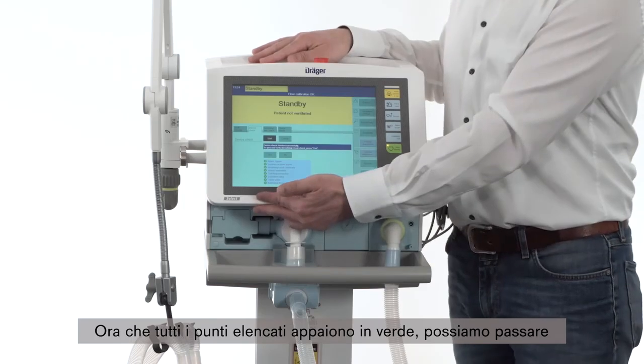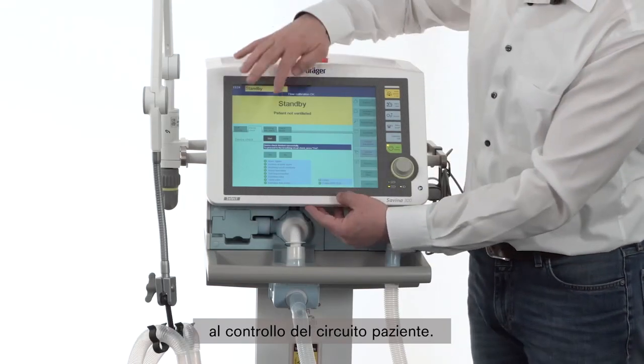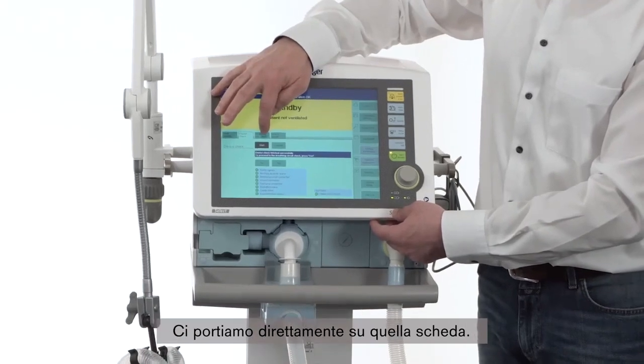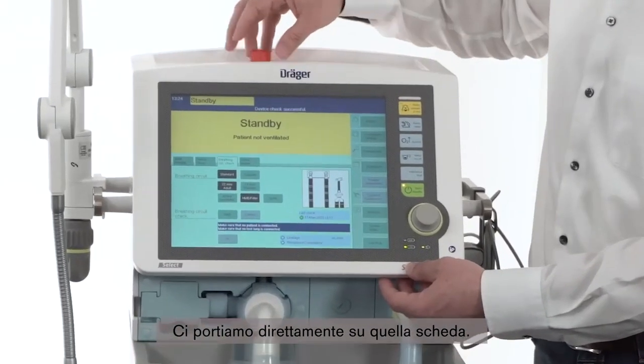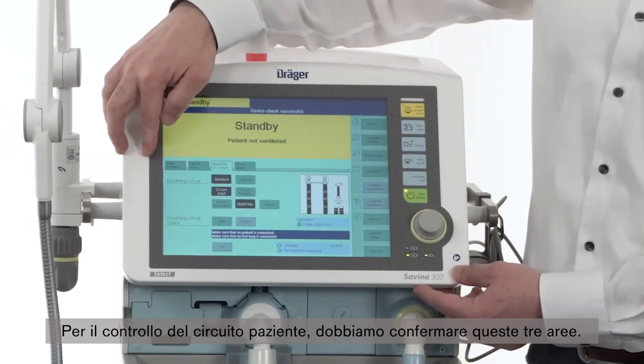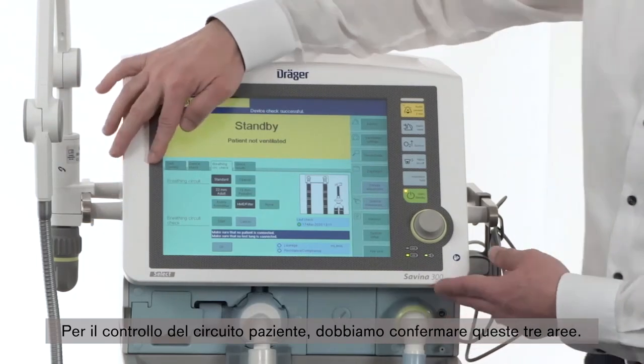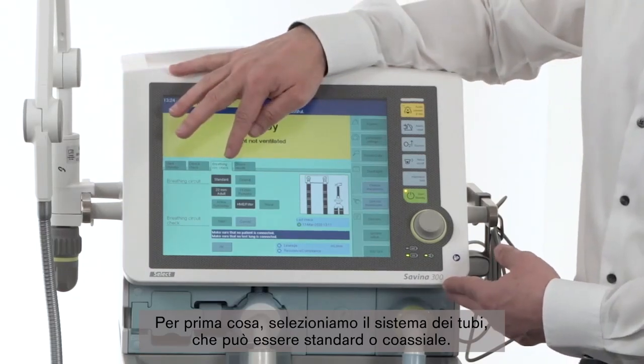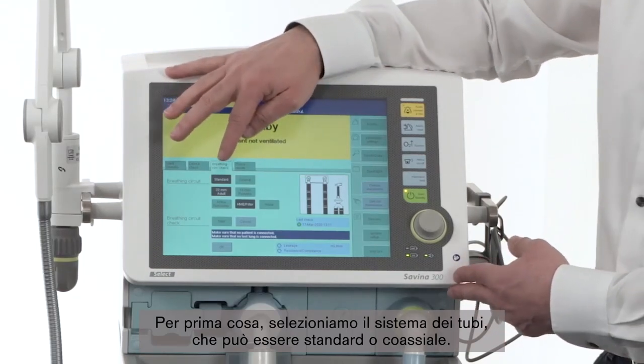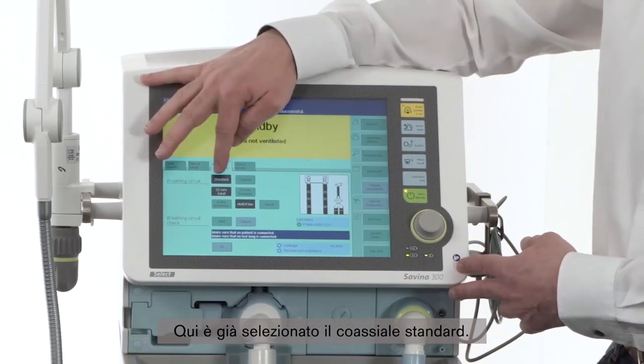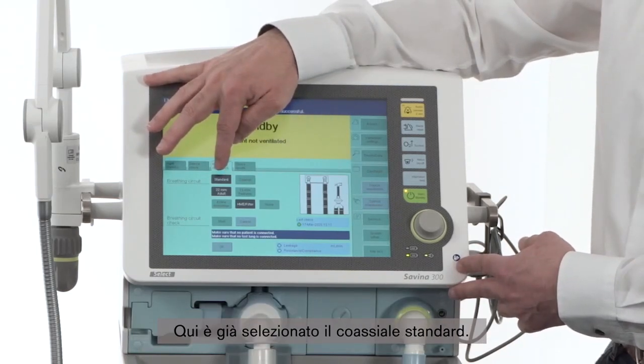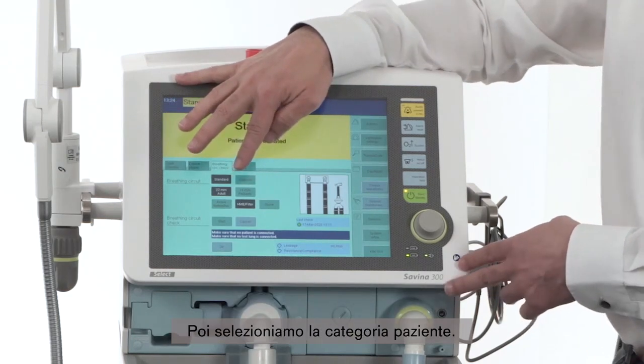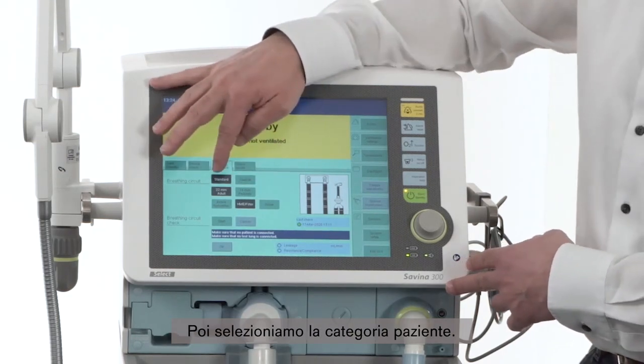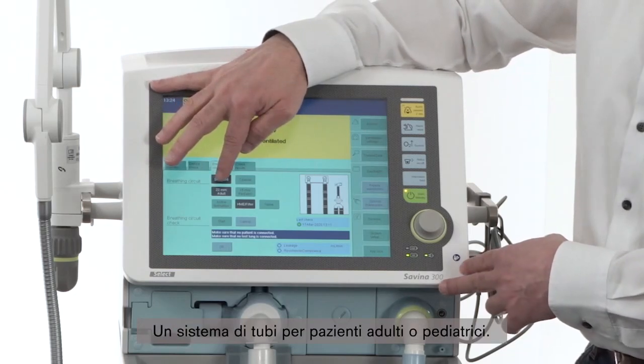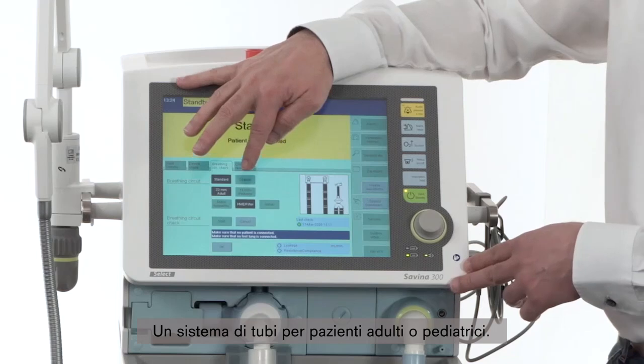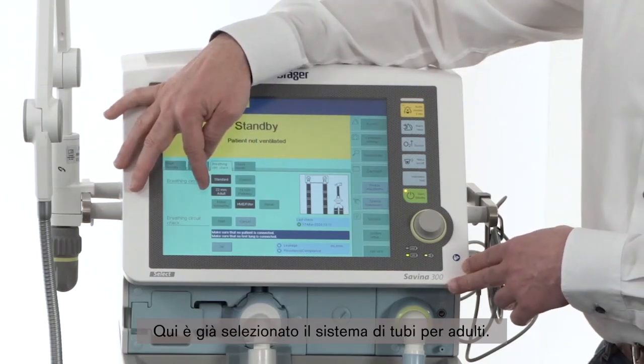All bubbles are green now, and we are ready for the next step, which is the breathing circuit check. So we are going directly to the breathing circuit check. In order to perform the breathing circuit check, please check those three areas. The first area is to select the hose system, which can be standard or coaxial. We have selected the standard already. The next one is to select the patient category, either an adult patient hose system or a pediatric hose system. We have selected the adult hose system already.